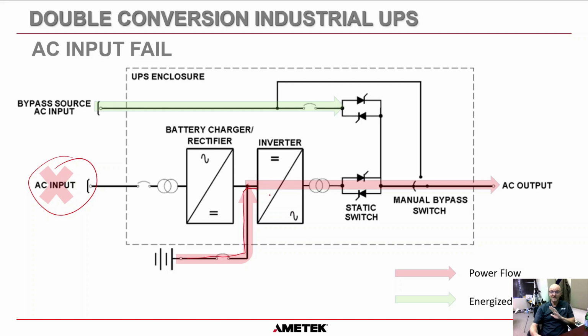The inverter has no idea, in truth, that the charger has failed. All it cares is that there is DC at the input, whether it's from the charger or from the battery. Obviously, it has to be of a substantial voltage within the ratings of the inverter itself. For our UPSs, for AMETEK Solid-State Controls for a 60-cell system, that is going to be between 105 and 140 volts DC. But as long as we have a battery here, we are good.